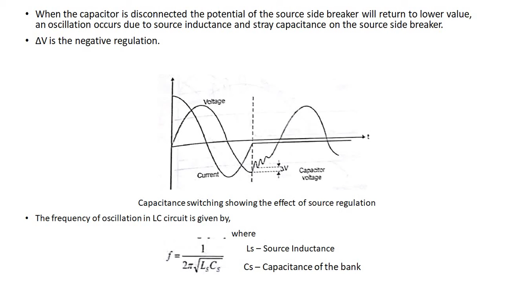Capacitance switching with restrike. Considering shunt capacitor switching, it is important to recognize restriking. In general, dielectric breakdown can occur in an interrupter at any time after initial arc extinction. When switching capacitor circuits, a breakdown within 0.25 cycle of initial arc extinction is termed reignition, but any time after this period is called restriking.